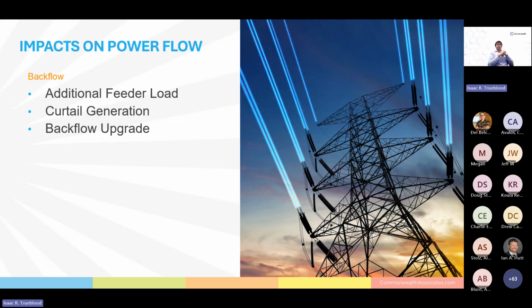You might be asking, so if we want to have distributed energy resources on our system, it can only be 20% of a single feeder. That seems pretty limiting. And you would be right, that is limiting. There are other mitigation options you can use. Depending on the distribution system's layout, additional loads can be relocated to that feeder. Alternatively, by upgrading the backflow capabilities of that single feeder, the distributed energy resource's generation is now applicable to all the feeders at that substation, expanding that 20% rule to apply for all the substation's feeders, not just the one feeder the distributed energy resource is on.